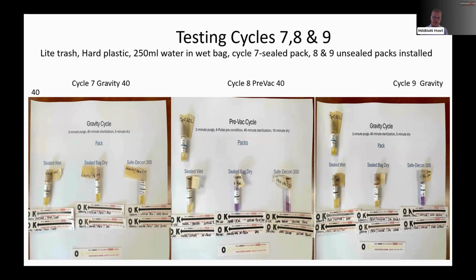And this was on the end. This is on the outside of the pack, inside the pack, as you can see. So we were getting the steam to it. We got the steam to here, but we didn't get the real penetration. And I don't know how much of this was just a lot of wetness built up. So you can see that all three failed. This was on a gravity 40. You're getting steam in there, but it just doesn't penetrate long enough.